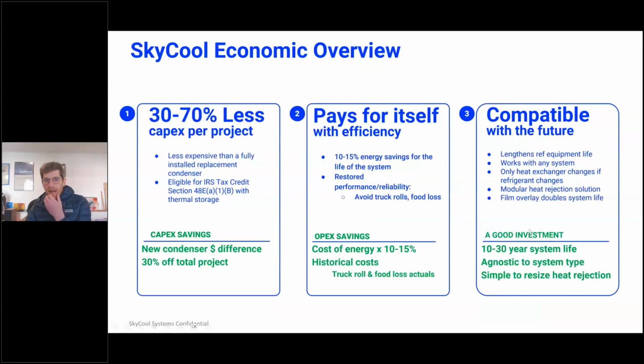In terms of economics and how we think about them, each project is unique. It depends on the existing cooling equipment, but generally what we're presenting for stores or sites where you have underperforming assets like a condenser, so instead of replacing that condenser with a new one, you can install our system, and it's going to have 30 to 70% less capex than say replacing the condenser. This is eligible for an IRS tax credit, and so there is an opportunity to also reduce that or improve whatever it is as a baseline if you add thermal storage. And I can answer questions about that if that's of interest.